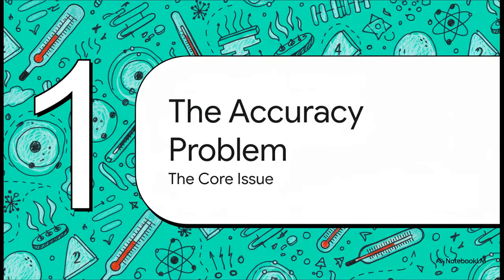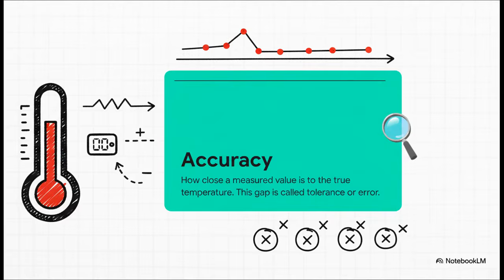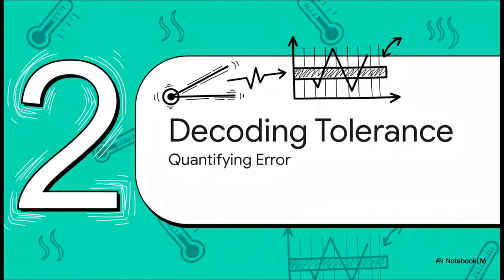Okay, so let's jump right in and pull back the curtain on the biggest issue, the one that most people completely overlook when they're measuring temperature. Understanding this is the key to everything else we're going to talk about. It all boils down to one word: accuracy. And all that means is, how close is the number on your screen to the actual physical temperature of the thing you're measuring? That little gap between what the sensor says and what's really happening, we call that tolerance or error. And here's the kicker. Every single temperature sensor, right out of the box, has some amount of built-in error. None are perfect. So if we know every sensor has this little bit of error baked in, how much are we talking about? How do we even measure it?